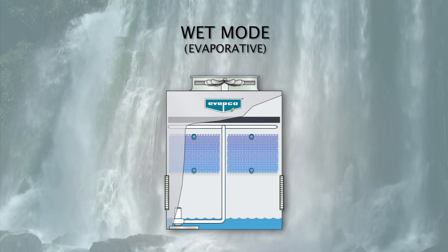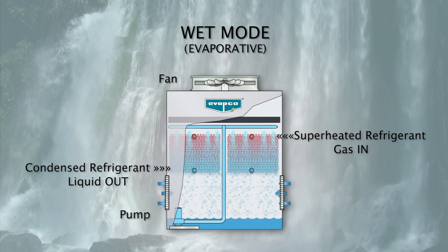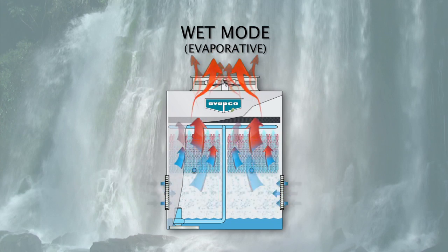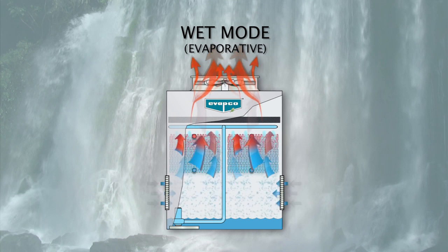In the wet or evaporative mode of condensing, the hot gas refrigerant enters and travels through the Elliptifin coil. The pump and fan are energized. The heat will be rejected efficiently using evaporative cooling, with only a small portion of the water evaporated. In the evaporative mode, the Eco-ATC will consume less energy than a conventional evaporative condenser.